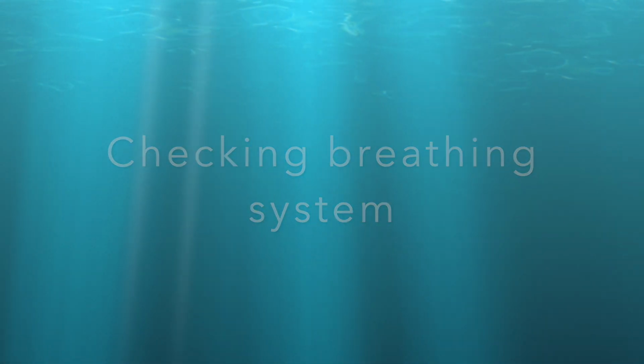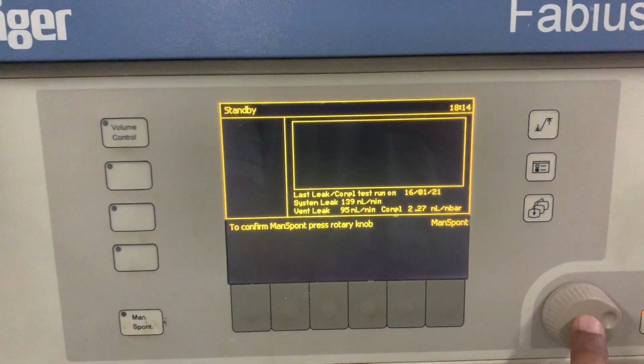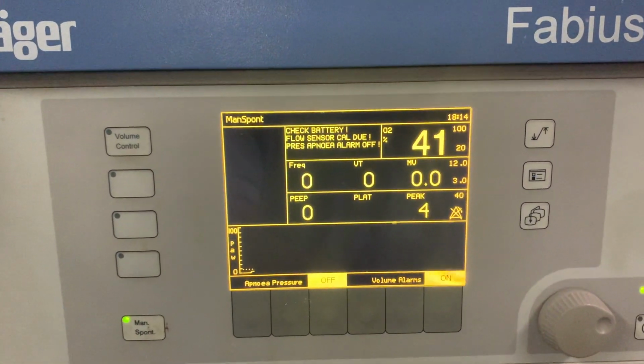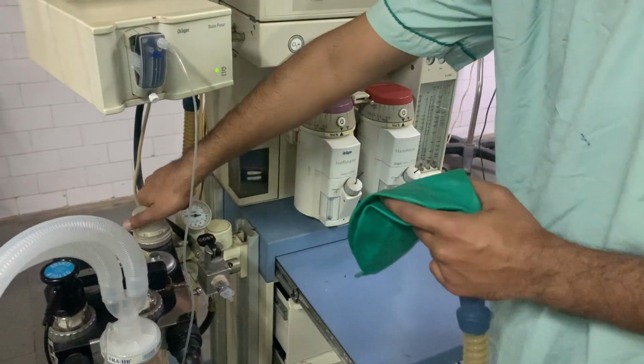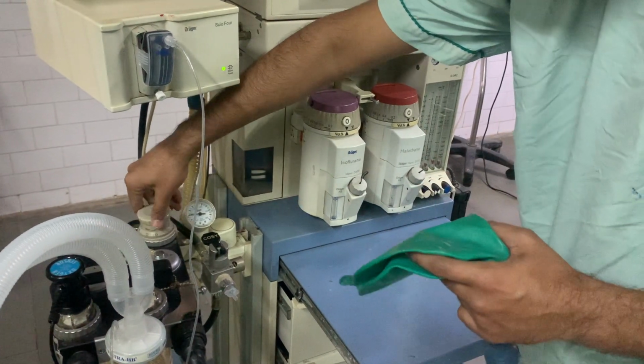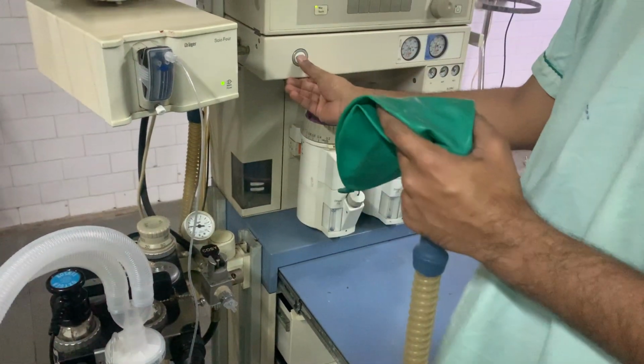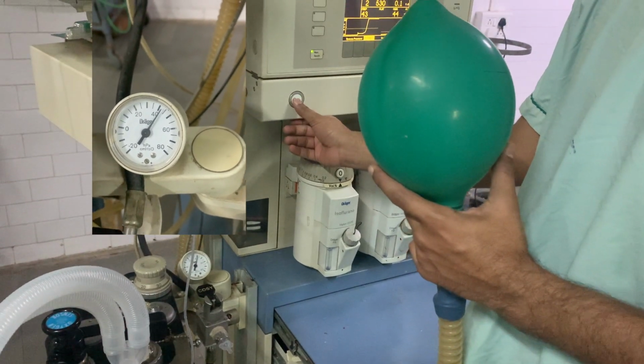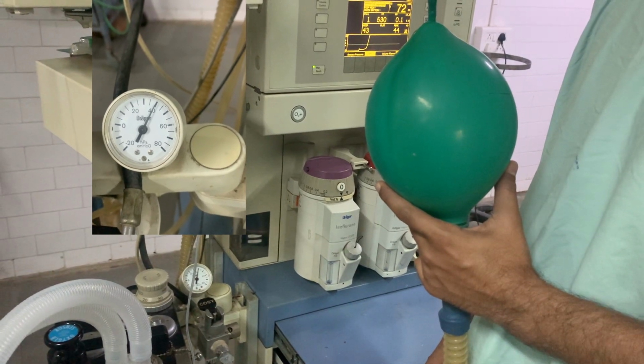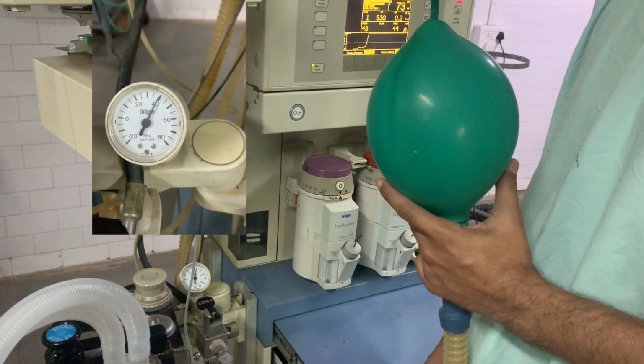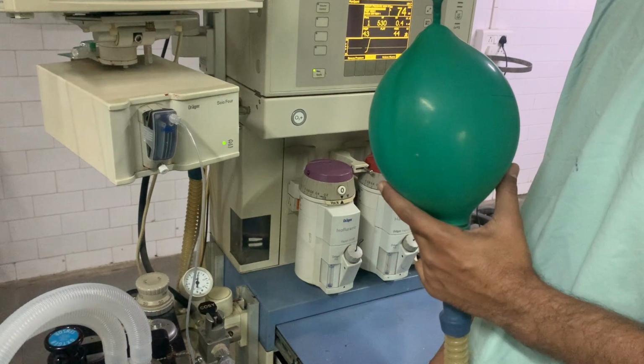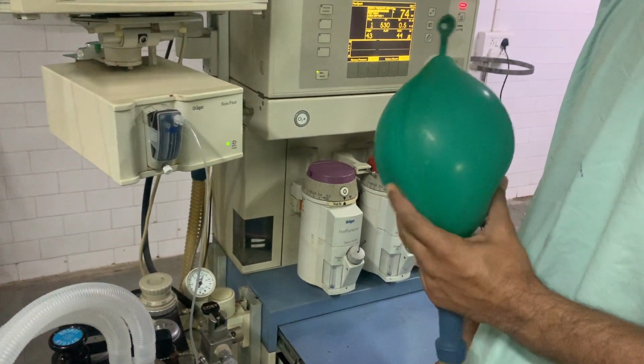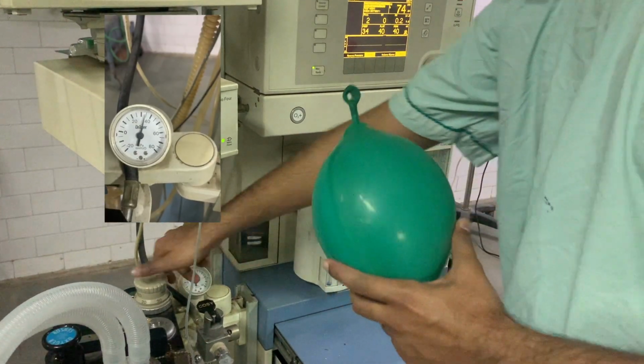To check the breathing system, make sure all gas flows are set to 0. Set the machine on manual or spontaneous ventilation or bag mode. Close the APL valve to 40 centimeters of water. Fill air in the breathing system to 40 centimeters of water with the oxygen flush. Ensure that the pressure remains fixed for at least 10 seconds. Open the APL valve and ensure that the pressure decreases.